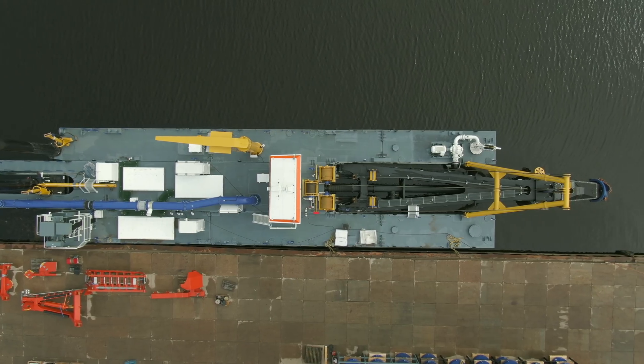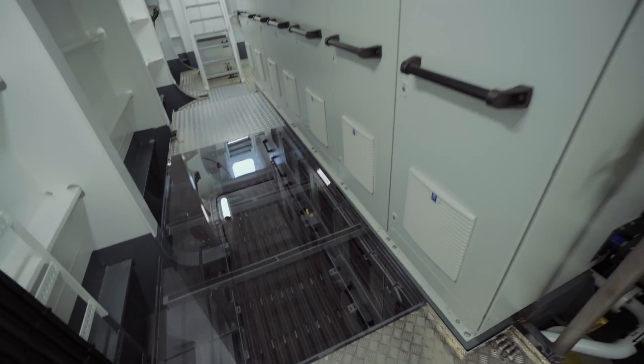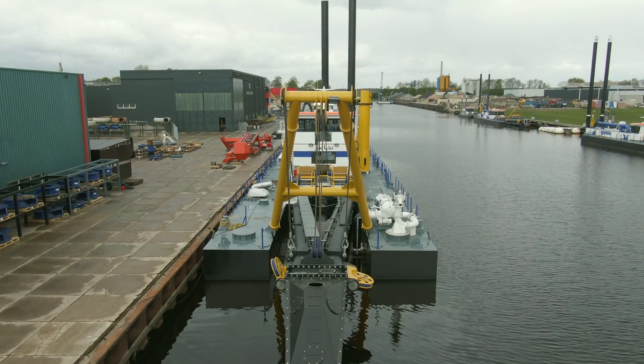The beauty of this project is that we already had the design ready. So all we did was we took out the diesel engines and we replaced them with electric motors and frequency drives. Of course we cannot put batteries or something in it — the power consumption is way too high. So you need to have some sort of a feed cable.